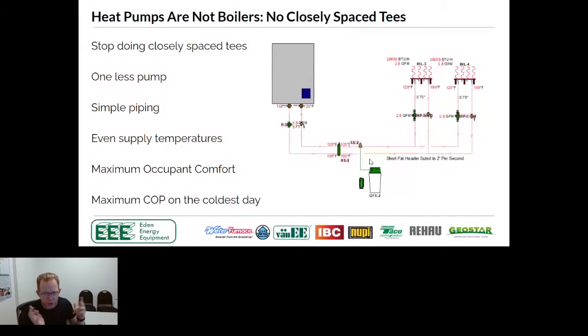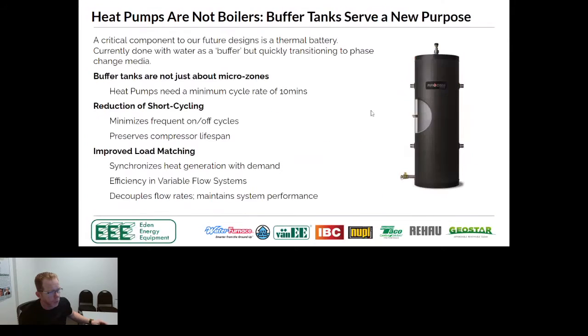So your wholesaler, your distributor, our technical team, whoever you deal with, can actually provide you with a complete package design. Or you'll find there are products you can buy off the shelf that'll take care of this. And we're going to show a few when we get into the next segment. So it's very simple piping. And the most important part is, if I'm putting on this a heat pump, then I'm not only maximizing the comfort, but I'm making sure that I've got the highest COP, being the coefficient of performance, to make sure it's working at its most efficient at whatever water temperature is being delivered to it.